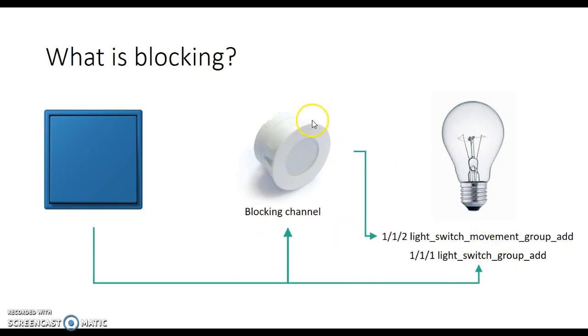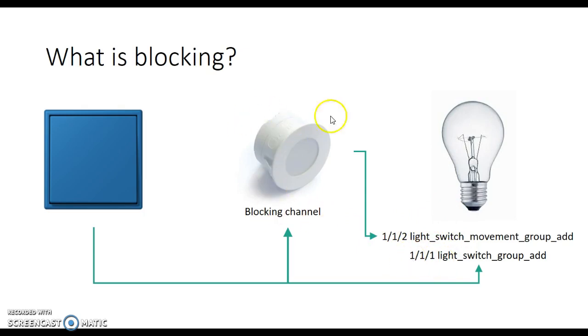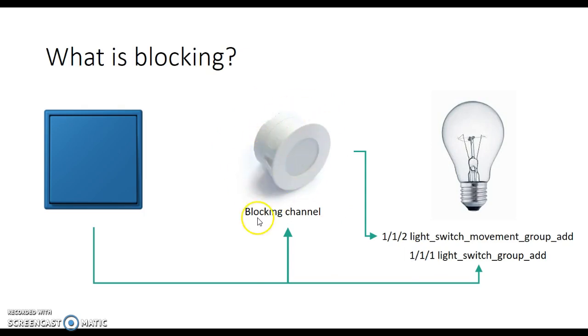And similarly with the movement sensor, you plug this in to a group address that will give you a one when there's movement and then at the end of the timer it'll send a zero. And the actuator will listen to both of these. But what you do is you also make the blocking channel on the presence, or movement object, listen to this light switch group address as well.